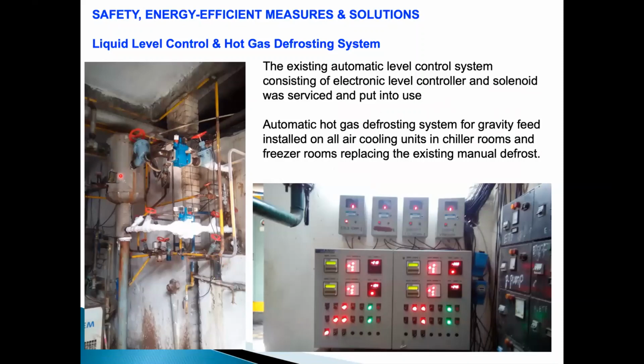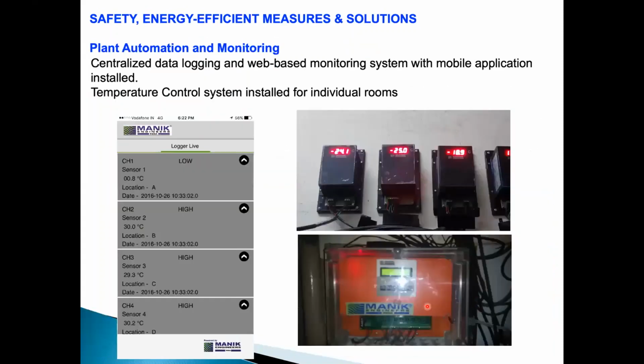See, all the old parts like evaporators and accumulators were maintained. It was only a retrofitting job conducted on the plant. So with the hot gas defrosting system, automation was implemented. So nobody has to decide or defrost the system. It was a real-time based system, programmed to operate at fixed time intervals in a day. So no need to go and check it. Then the major requirement of the owner was to have remote monitoring. He is a busy man traveling in India and abroad, and he wanted to monitor everything on a mobile. So a data logging system with local displays was provided, and he can now monitor everything on a mobile.